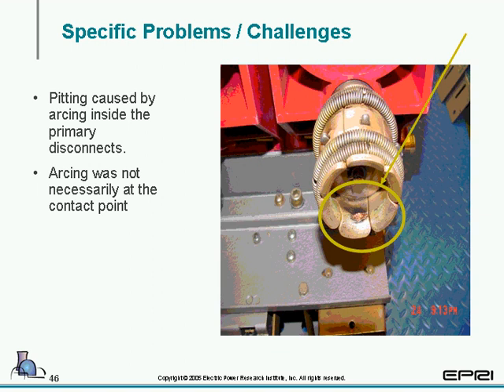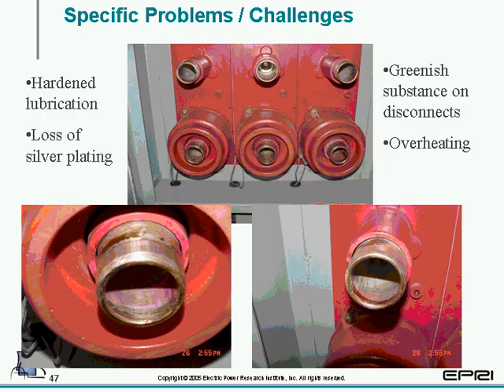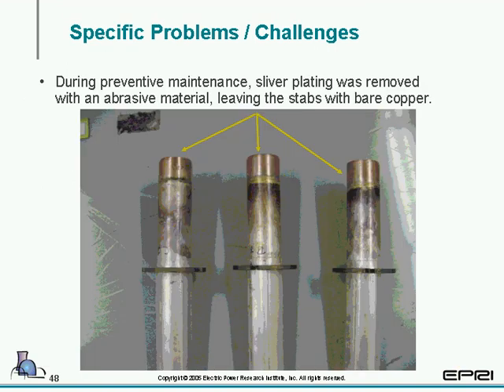We started looking at the primary disconnects. Again, we could see where you had splatter or pitting effect on the primary disconnects. That led us to look inside the cubicles. When we took them apart, we found hardened lubrication on the bushings, loss of silver plating, greenish substances, and overheating as well. We removed the bushings and found that over years they had used an abrasive pad, and they had literally removed all of the silver plating, leaving bare copper.